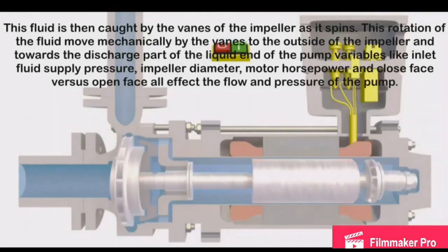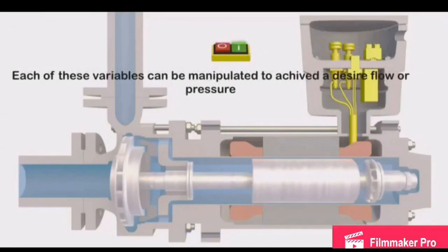This mechanical movement and discharge pressure of the pump varies with inlet fluid supply pressure, impeller diameter, motor horsepower, and closed-face versus open-face. All of this will affect the flow and pressure of the pump. Each of these variables can be manipulated to achieve a desired flow or pressure.